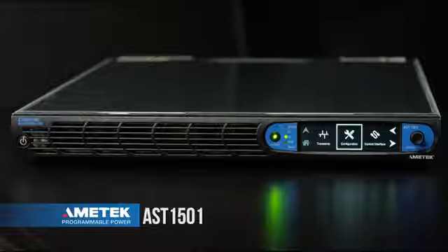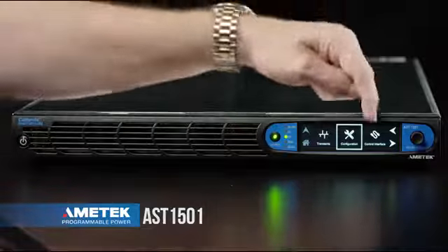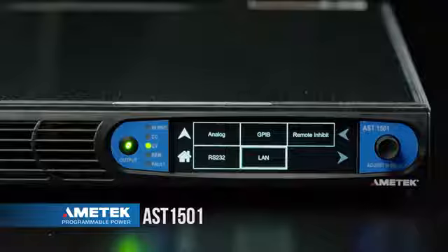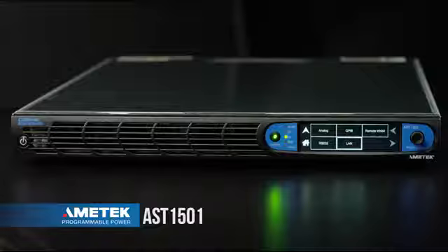next up is our selection for control interface. Selecting control interface allows us to set GPIB address, RS-232 parameters, LAN parameters, as well as analog selection for setting our analog programming. Our behavior for remote inhibit is also selected from this screen. Going back to the home screen.